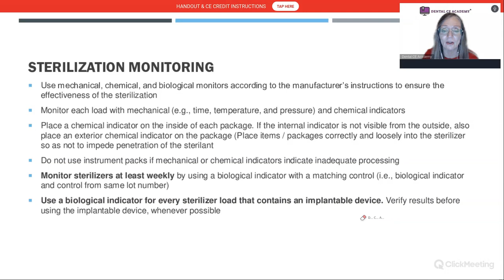So we want to make sure that we're using, and there are different tests available. I prefer spore testing in office because then we know we can put our instruments back into service. If you're sending a strip somewhere and you're waiting for the results online, and you've already put those instruments in service, they may not be sterile, right? You should monitor your autoclave at least weekly. If you're autoclaving many more instruments than normal practices, like here at the clinic, we had to monitor daily because we're processing several thousand instruments a day. And you may see that on your quiz.